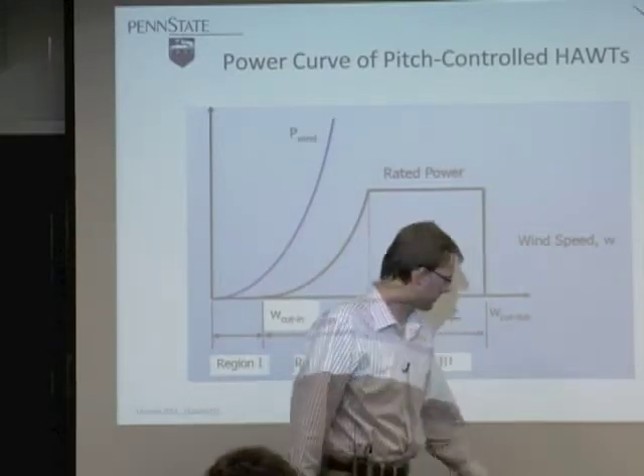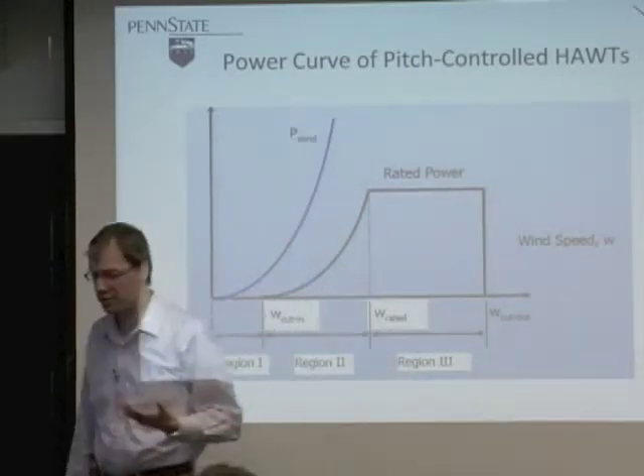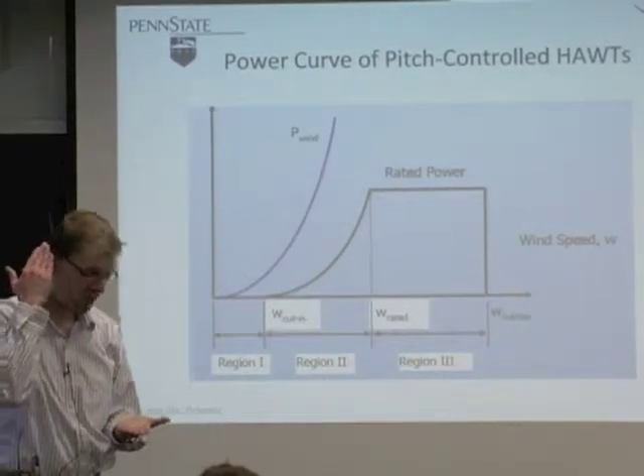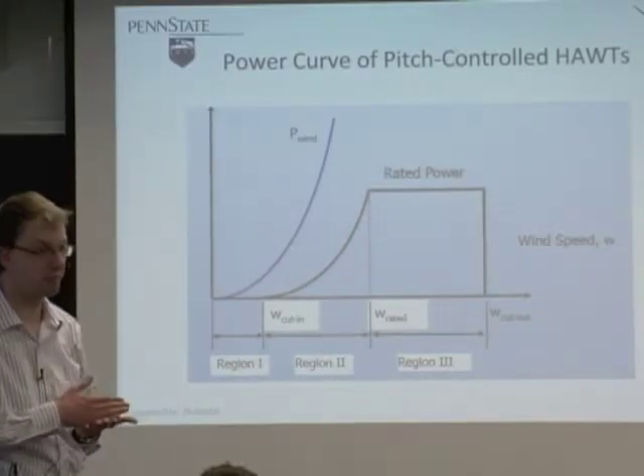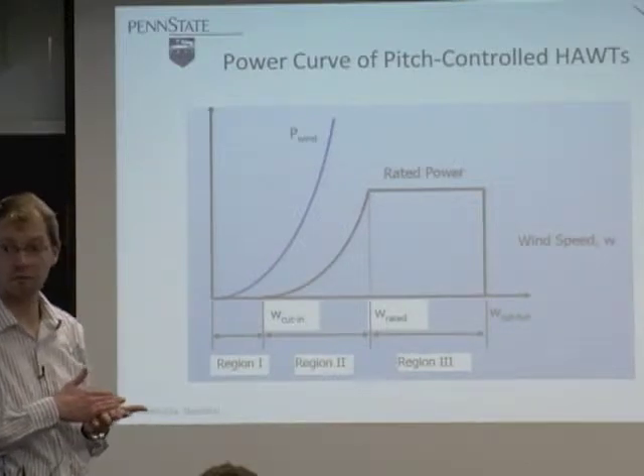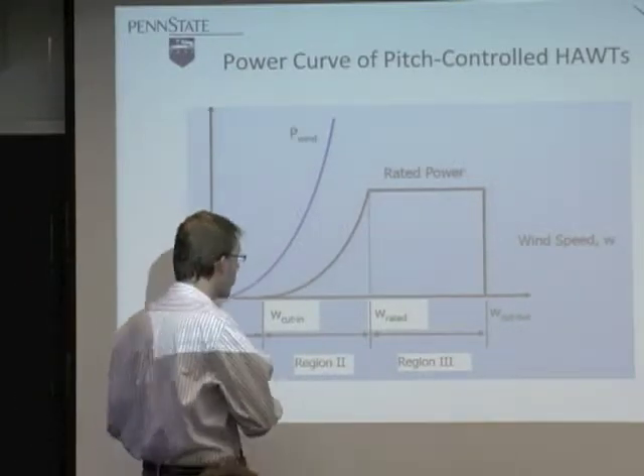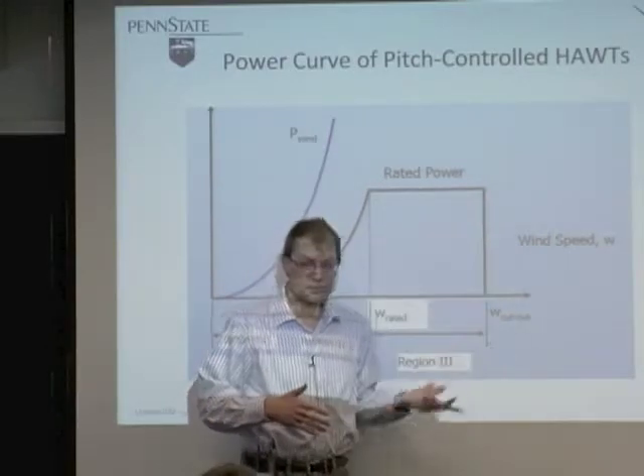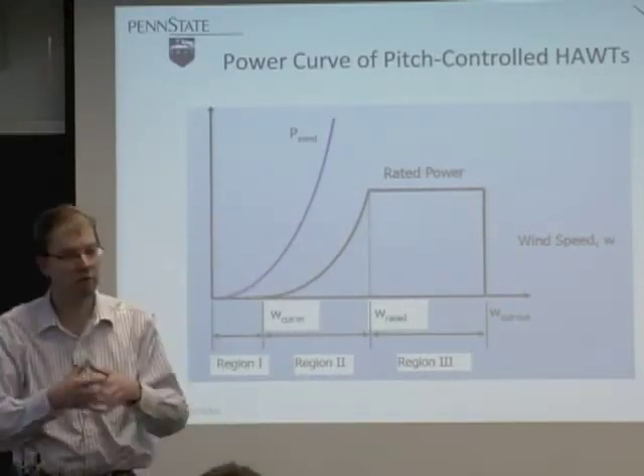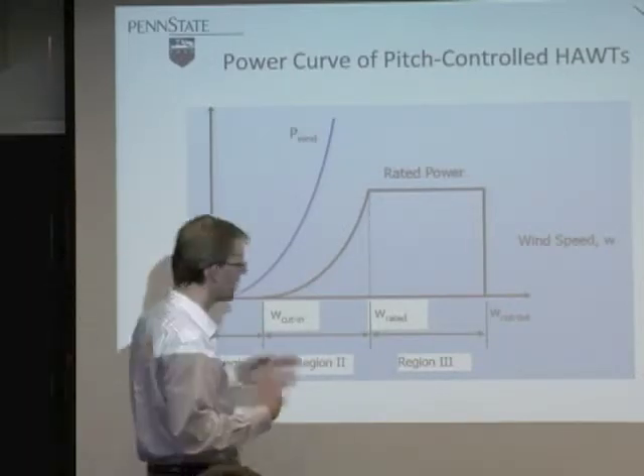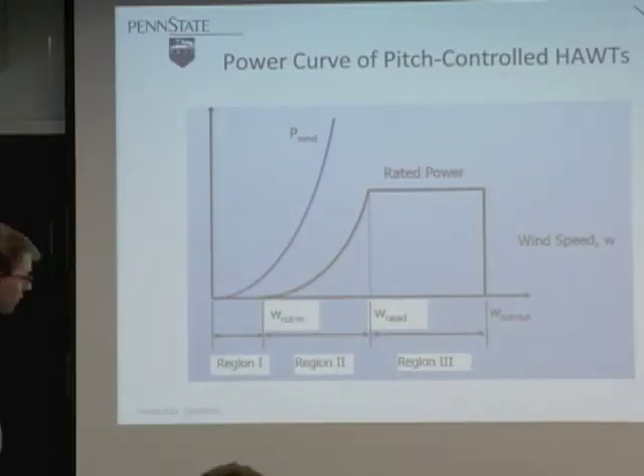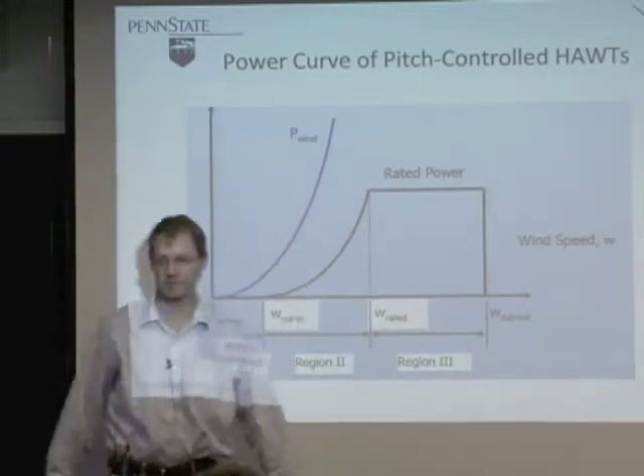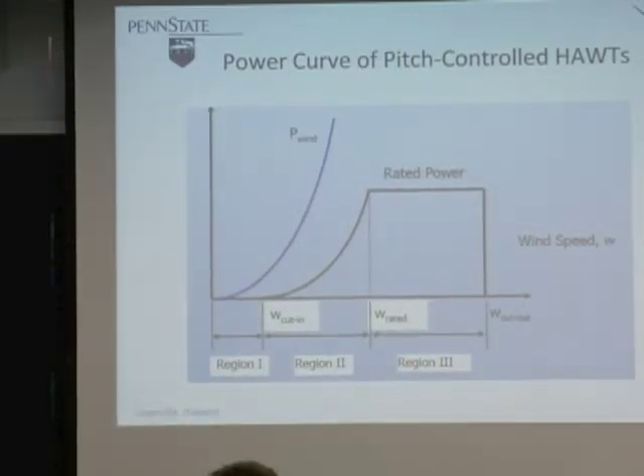Then, at the end, usually if the wind speed becomes about 25 meters per second, you have to shut down the turbine. It's not a generator problem — it becomes a blade load, a load and fatigue issue. In storm conditions you also have more fluctuations with large amplitude, and that poses a problem, so you have to shut down the rotor. That's the cut-out wind speed. So we have these three distinct regions in the power curve of a modern pitch-controlled horizontal axis wind turbine.